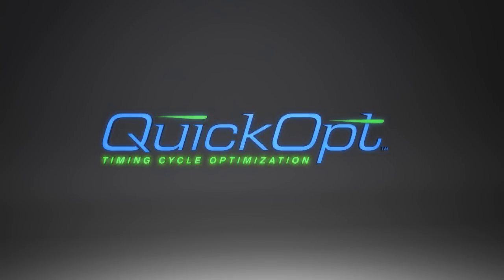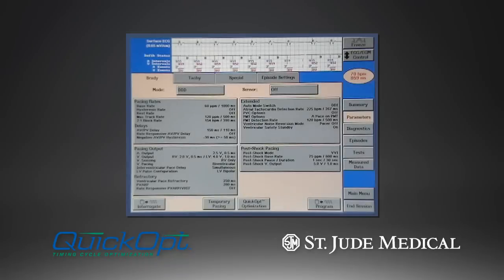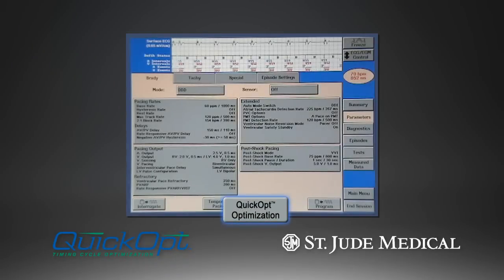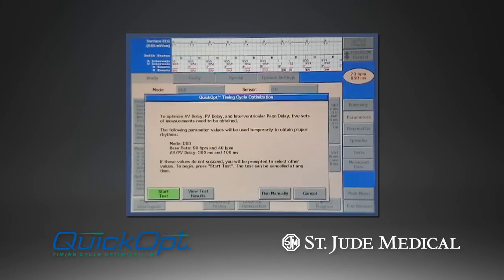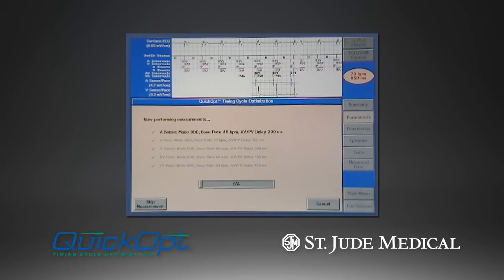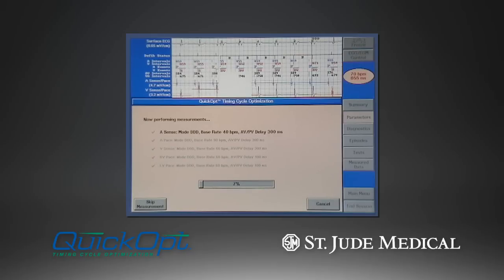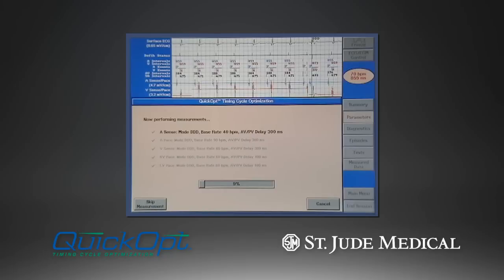But there is now a quick and effective way to optimize the timing cycles of CRT patients. Exclusive to St. Jude Medical, the QuickOpt timing cycle optimization algorithm electrically characterizes the conduction properties of the heart and calculates optimal AV, PV, and VV delays at the push of a button. During any device follow-up, the clinician can simply push a button, and in about a minute, the optimal AV, PV, and VV delays are calculated.